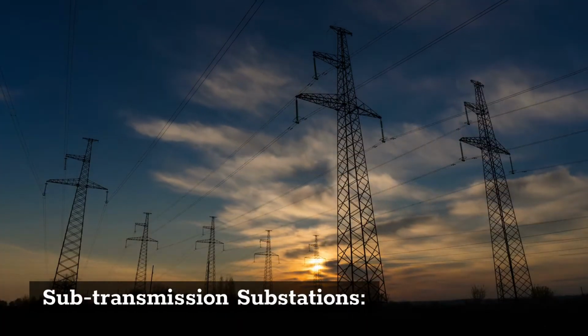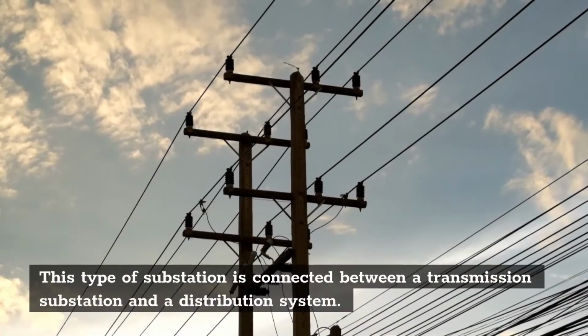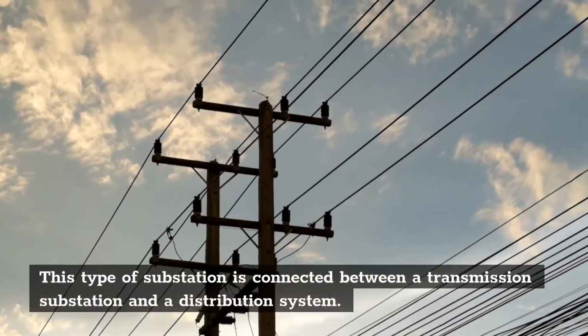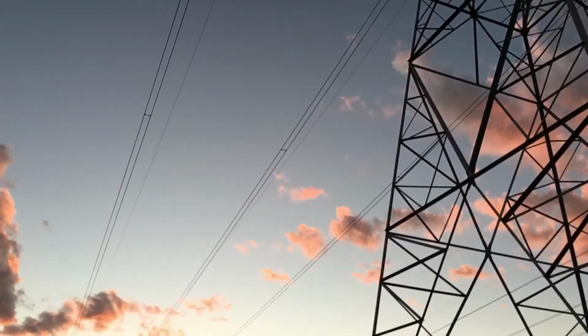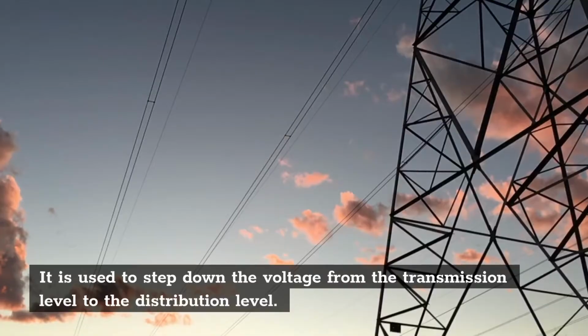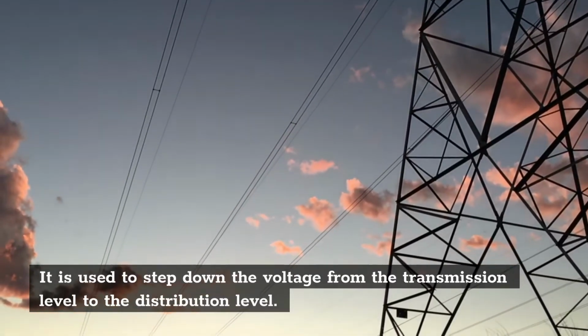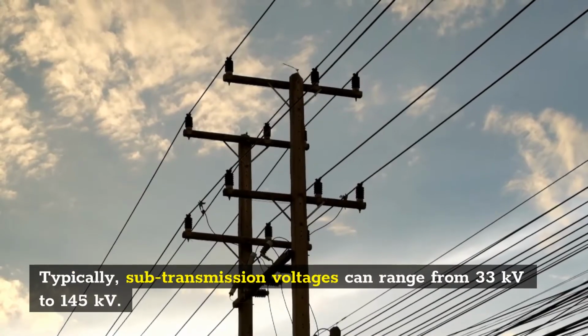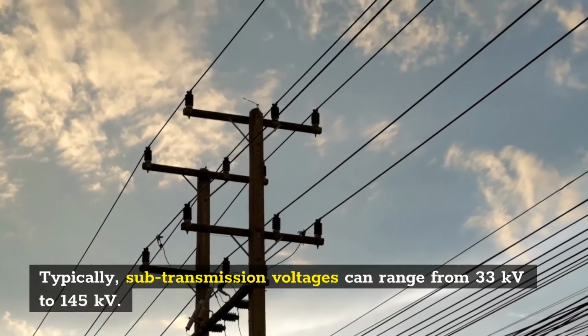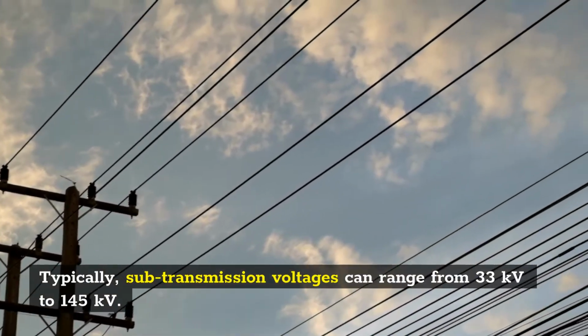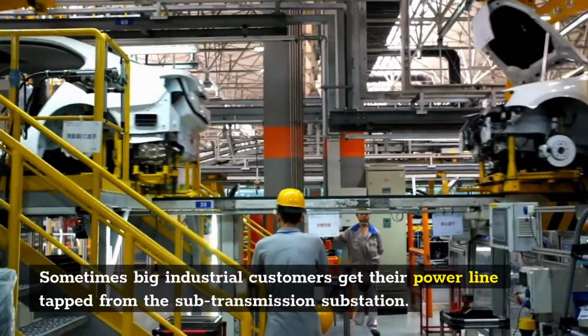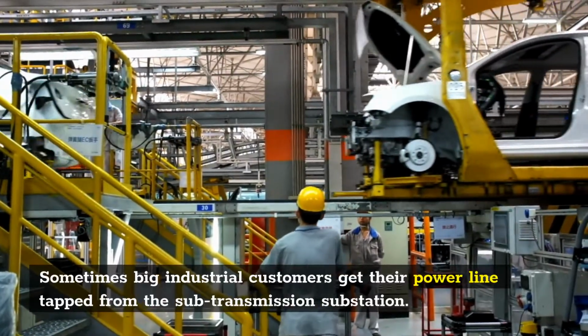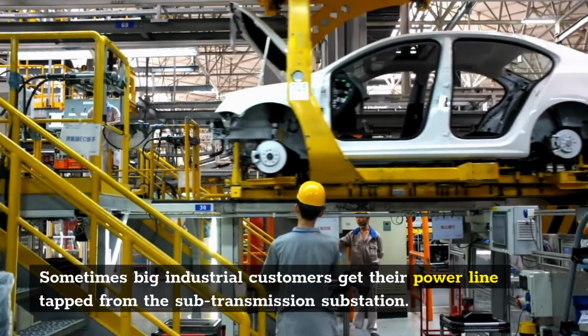Sub-transmission substations. This type of substation is connected between a transmission substation and a distribution system. It is used to step down the voltage from the transmission level to the distribution level. Typically, sub-transmission voltages can range from 33 kV to 145 kV. Sometimes big industrial customers get their power line tapped from the sub-transmission substation.